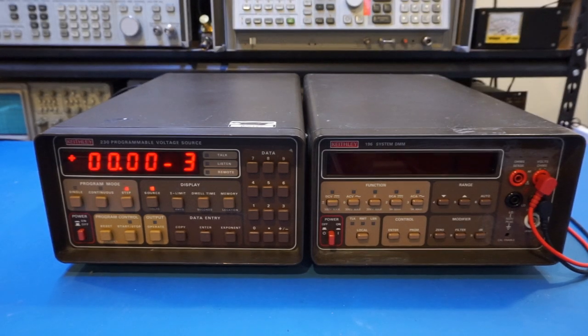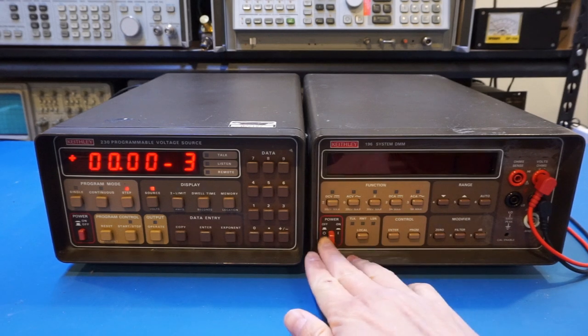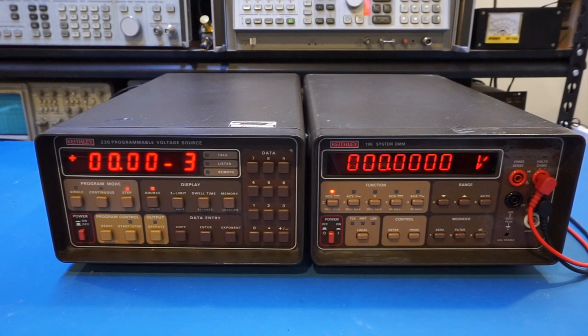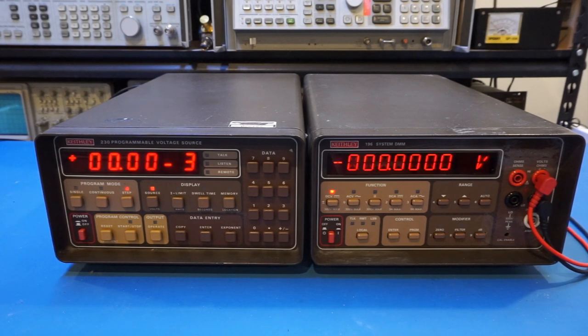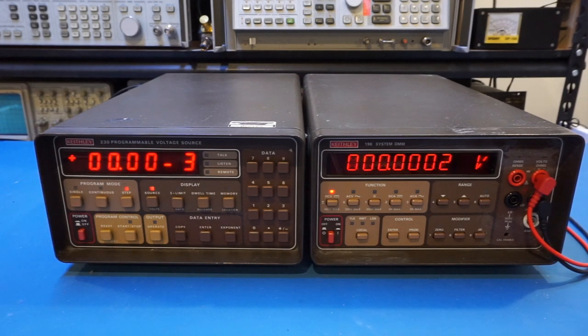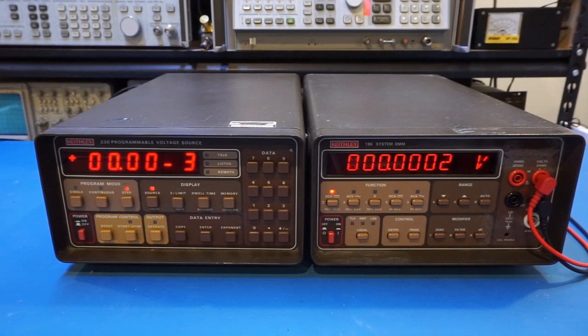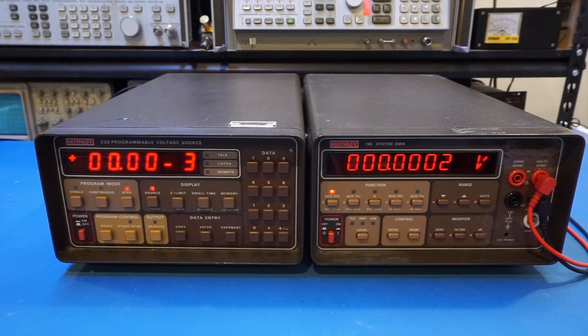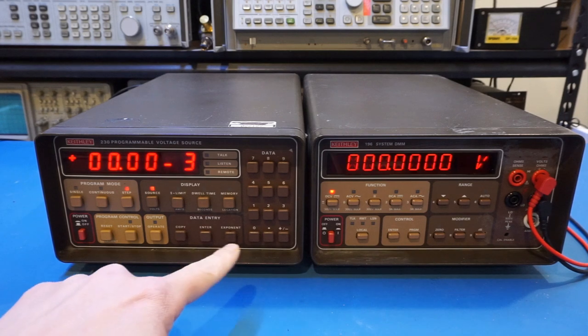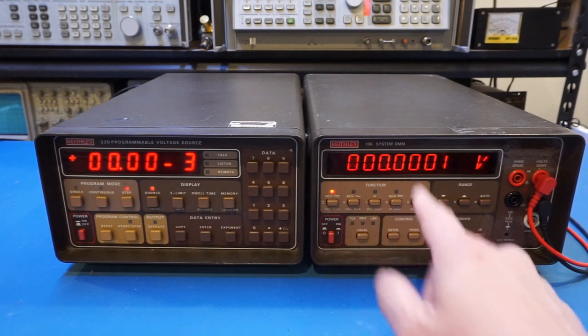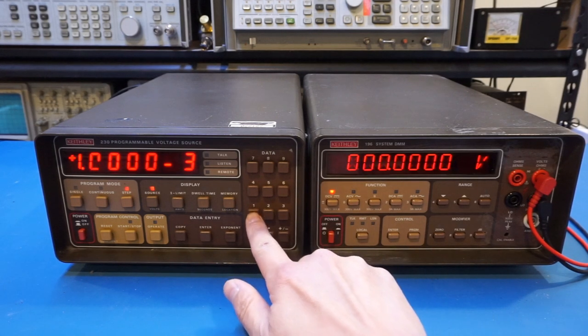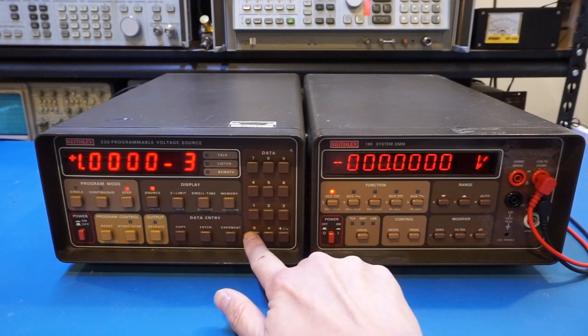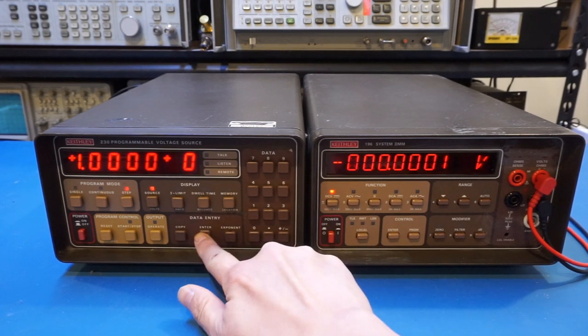Upon powering up, you can see that we're outputting zero. So let me power up this 196, and no problem at all. I thought first let's set up a voltage. Of course, for this to be in spec, you have to let it power up for about an hour at minimum. But right now we're not going to wait for that long. So let's just punch in some numbers here. Let's say we wanted to set up one volt, and the use of this is very intuitive. So source, and let's try this out. I haven't read the manual yet, but it should be pretty intuitive here. So we do one volt, and this is minus three, so it's millivolts. So I assume we do 1000, and enter.